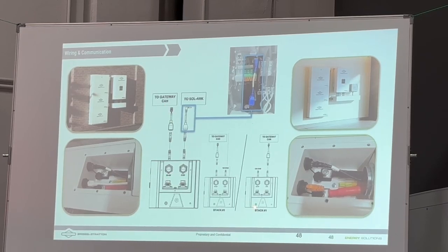Let's suppose you weren't using a Sol-Ark, you were using some other inverter that we maybe don't support, that we don't have closed loop communication with, and you wanted to use maybe an Outback inverter, although we're working on that. You wanted to use an Outback inverter that doesn't have closed loop with the same battery, you can do that. You just would use that terminating resistor in the battery, right, to tell it there's no connection to the inverter here. So we put a terminating resistor, and then we would bring the CAN bus into the gateway.